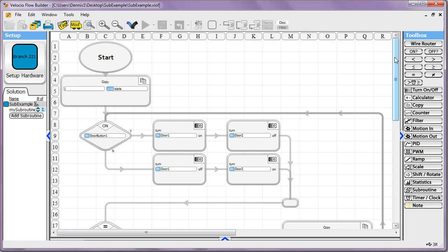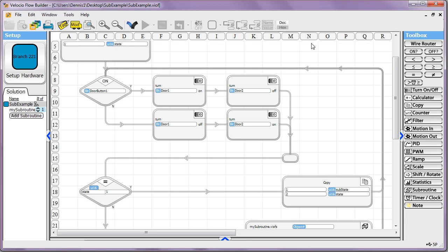So subroutines, just like everything else we do, we want to have them enter their routine, check some logical states, respond to however they need to, and then move back on. Go to your main loop and check the important stuff there. What we want to ensure is that we're never locking up in a particular condition that prevents us from checking valuable inputs, the states that may be very important that we need to be checking on all the time. We don't ever want to lock ourselves up in a case where we're ignoring those.